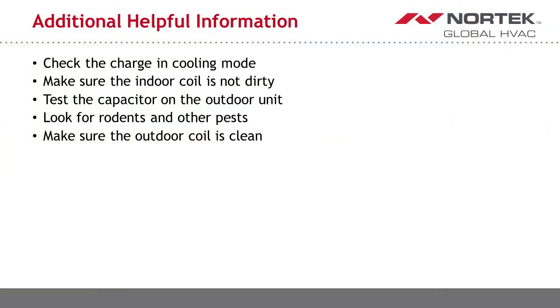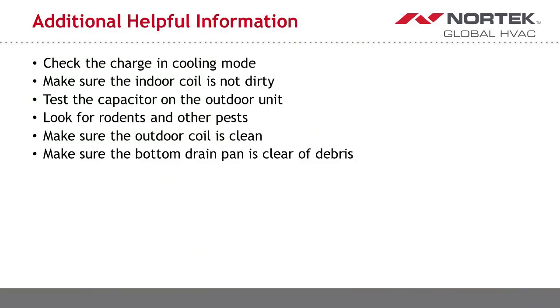Other things to look for: the bottom pan of the condensing unit. Something that, in my opinion, is often overlooked. If you've got a bunch of debris and buildup in the bottom of that pan, your drain holes are blocked up. So when the heat pump goes into defrost and all that defrost water is trying to get away, if debris is blocking it from getting out before it refreezes, you're going to start getting ice dams in the bottom of that heat pump, which can eventually damage it. So make sure that bottom pan is clean and free so that the heat pump can drain.